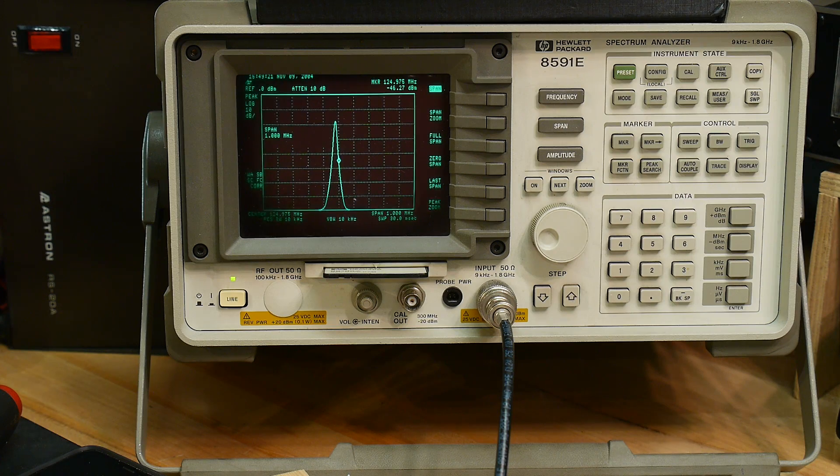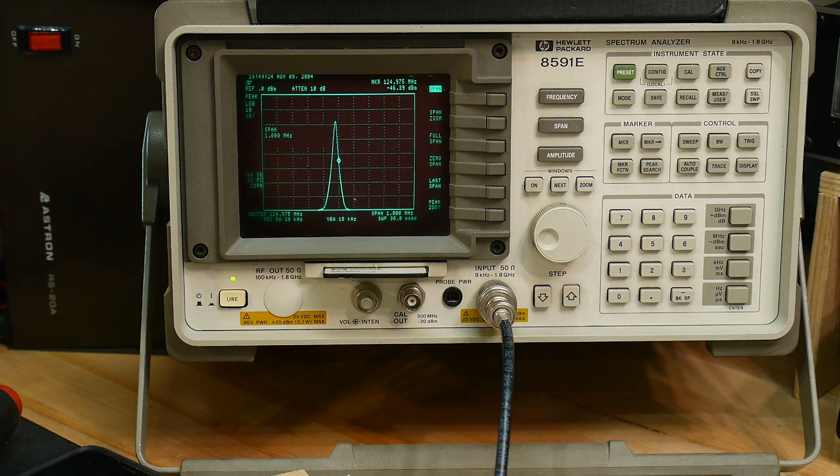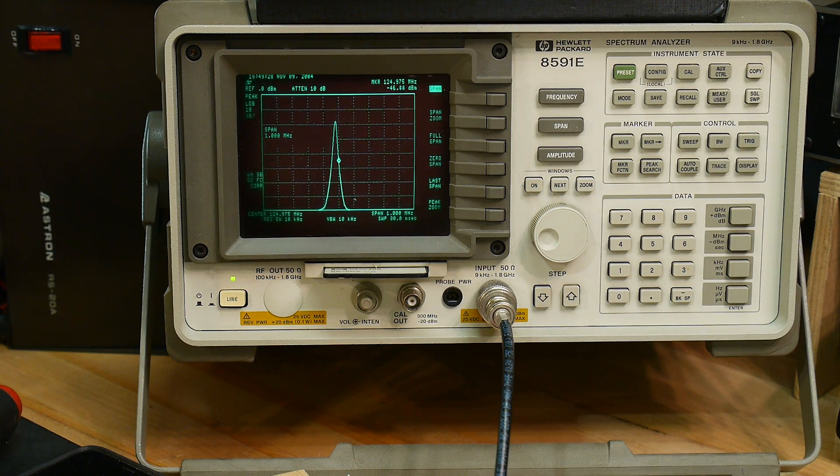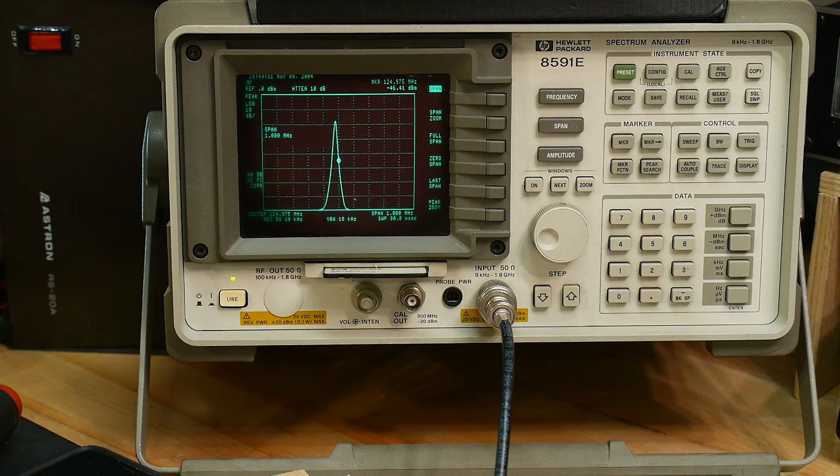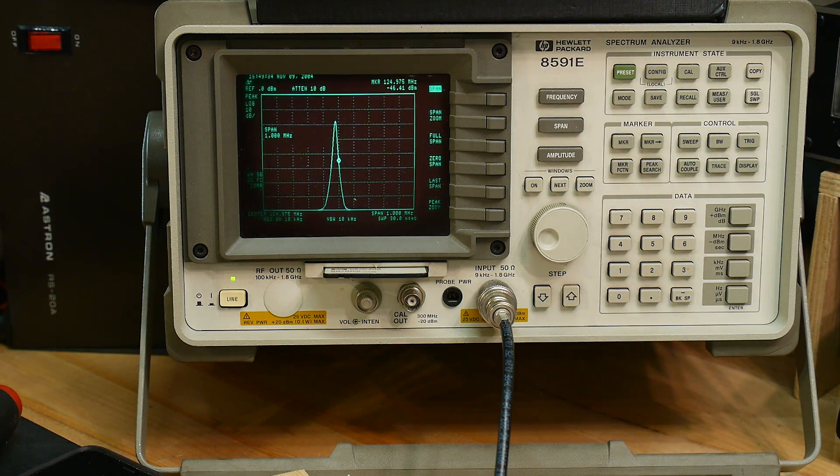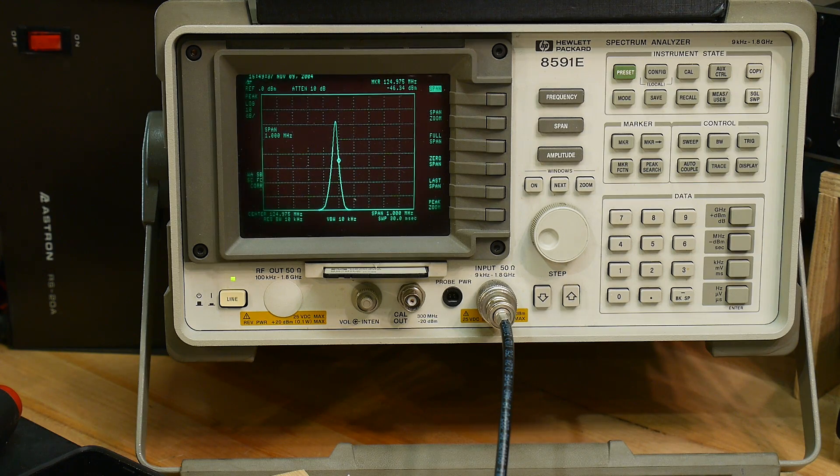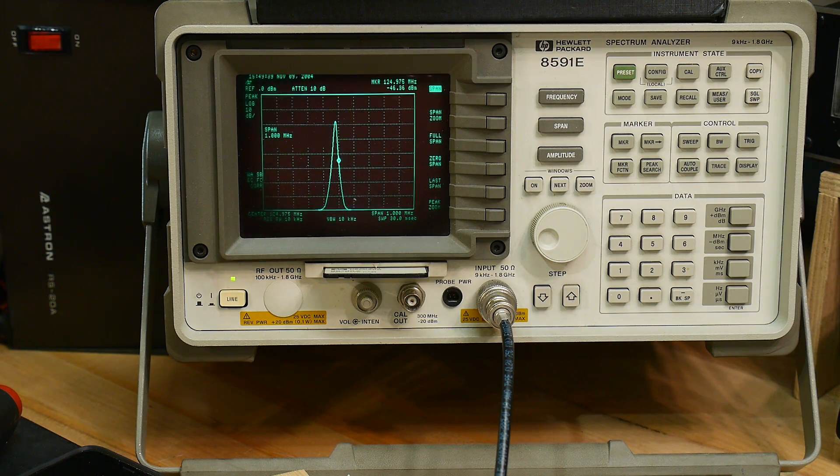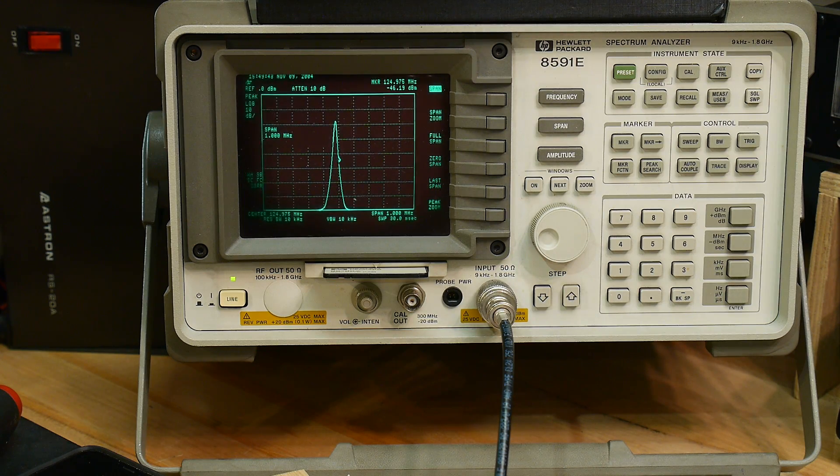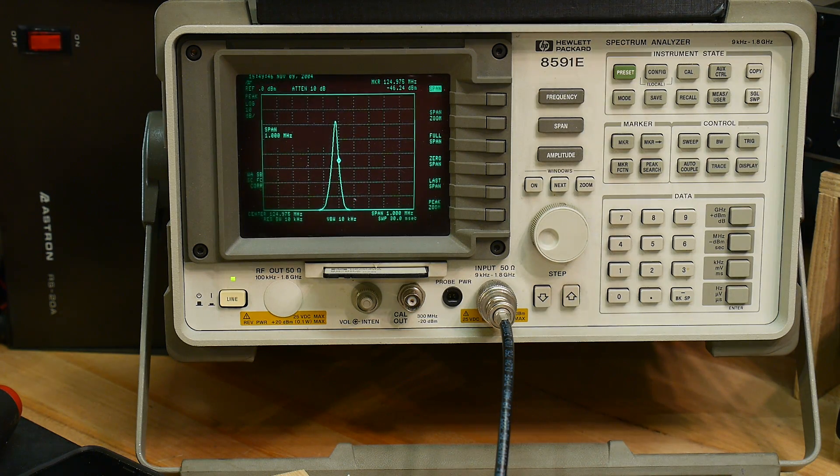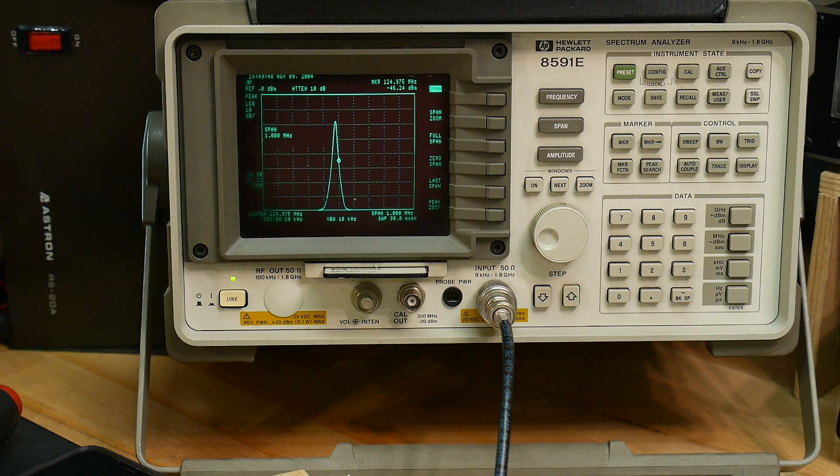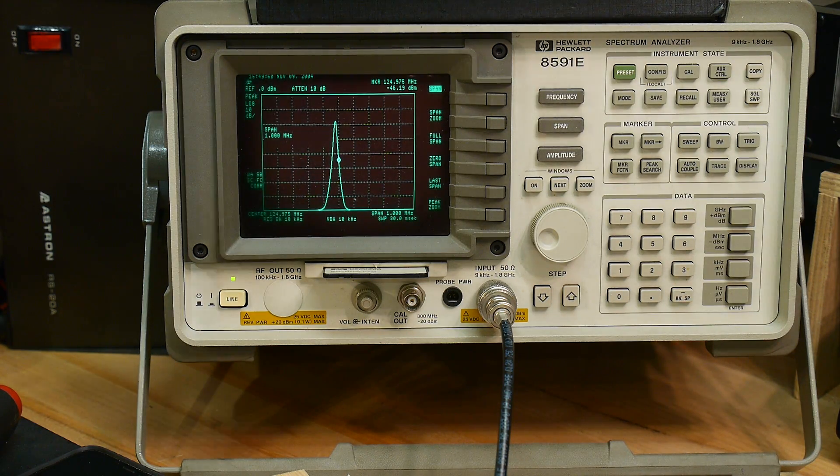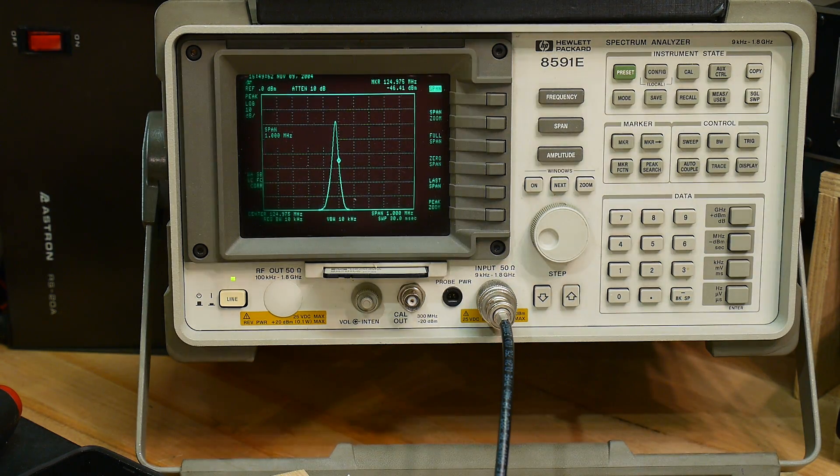But the very first thing it did when it woke up said was using default data. So it had erased all of the CAL data in the instrument. Now, luckily, two of my viewers had told me the very first thing you do when you get one of these things is document all of your CAL data. And it's not digitally documented, it's write it down. So let me show you that in case you ever have one of these things.